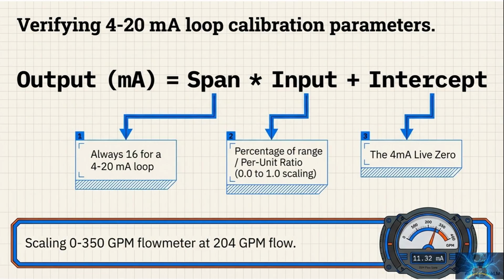Verifying 4 to 20 milliamps loop calibration parameters. This slide is a calibration sanity check tool. Output current in milliamps follows a simple linear relationship. Span times percent of range plus the intercept. For a 4 to 20 milliamps loop, the span is always 16 milliamps. The input is the percent of range, also called the per unit ratio, from 0 to 1. The intercept is the 4 milliamps live 0. The example is a 0 to 350 gallons per minute flow meter at 204 gallons per minute.